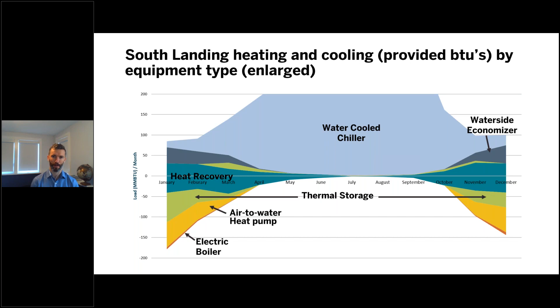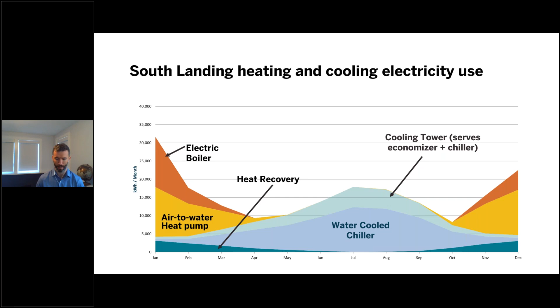Now I'll ask you to just keep your eye on that little orange sliver down the bottom that represents electric boiler as we move to the next slide. This next slide actually represents the amount of electric energy required to operate the equipment to meet the load. And you can see that even though that electric boiler only makes up a very small proportion of the load served, it does consume a disproportionate amount of electric energy, and it actually becomes a significant driver behind our annual utility peak. Next slide, please.